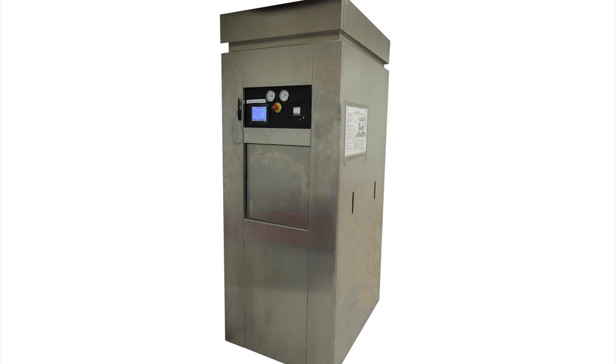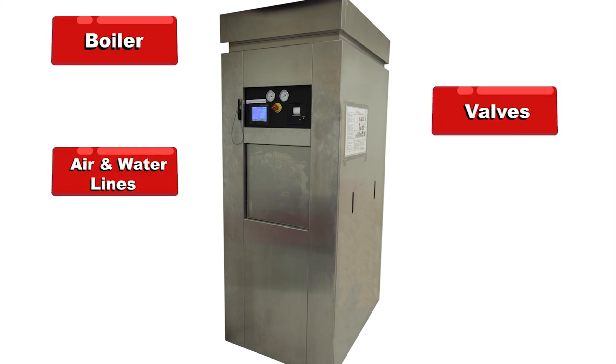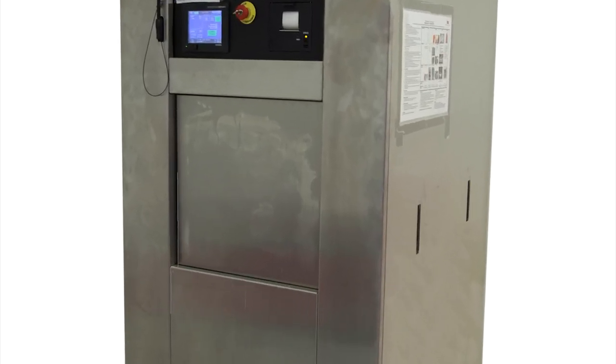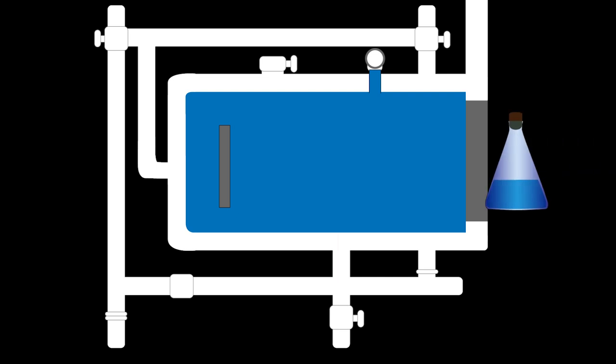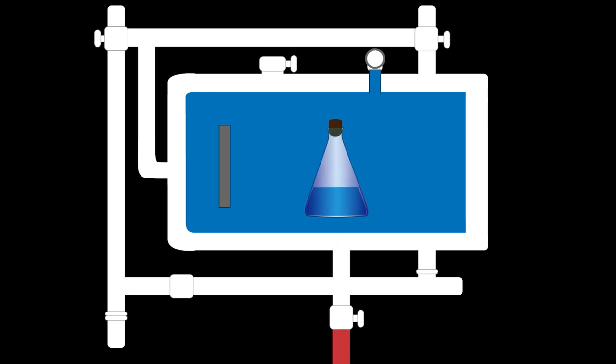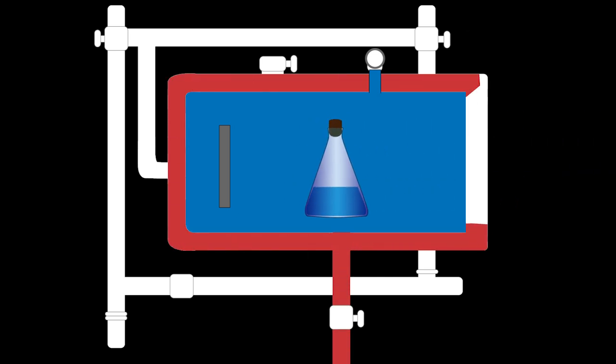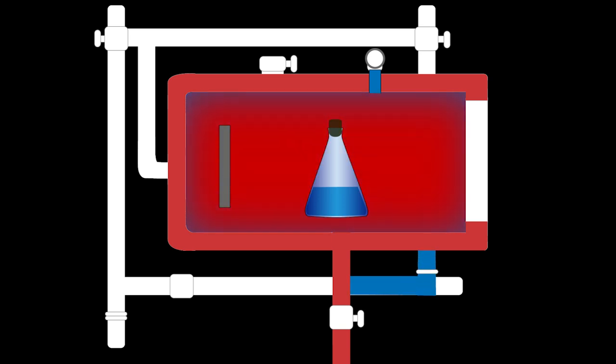What we don't see are the boiler, valves, air and water lines, gaskets, and several other parts that make this autoclave work. Once the door is closed and properly sealed, steam enters the chamber and pushes air already in the chamber out through the drain. As steam enters the autoclave, the chamber temperature and pressure rise, but the jacket pressure remains constant.